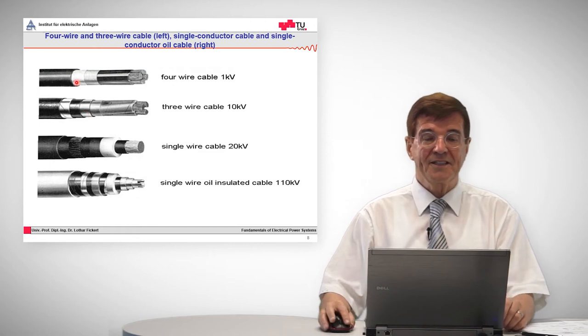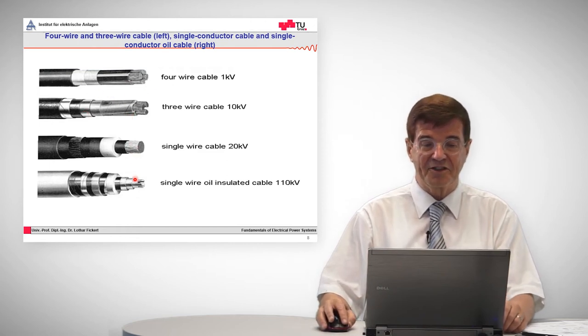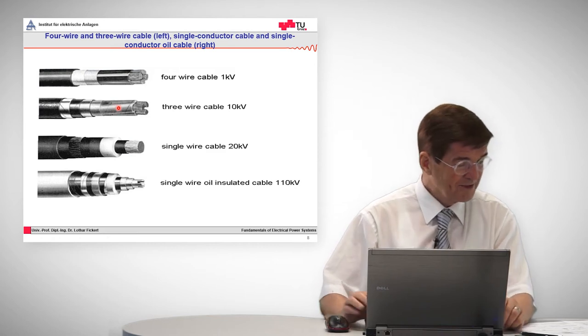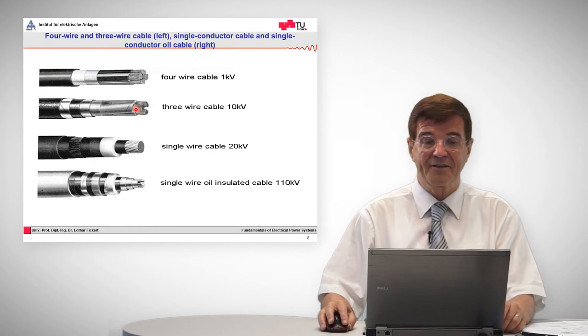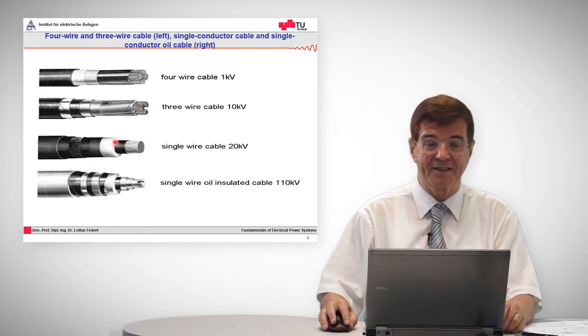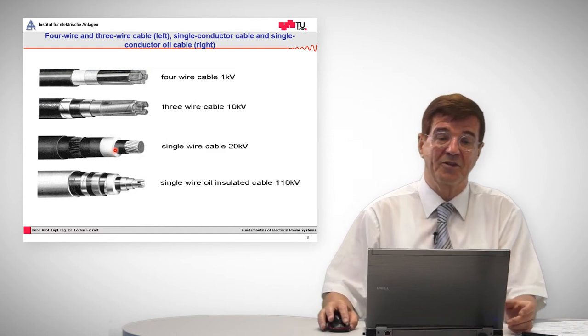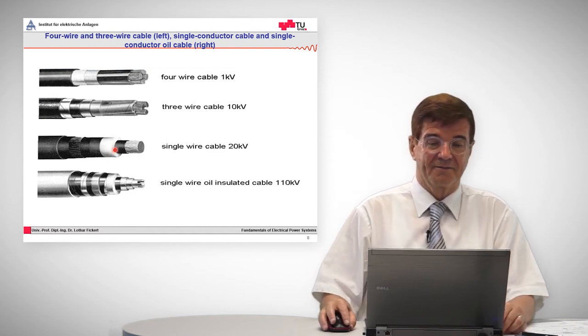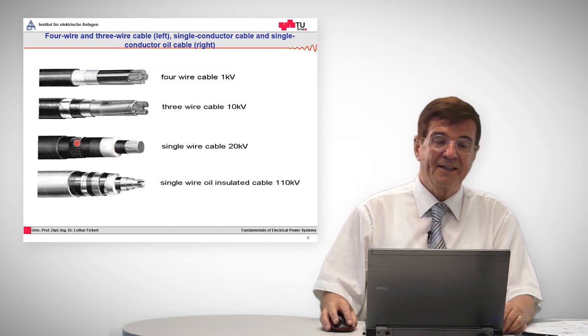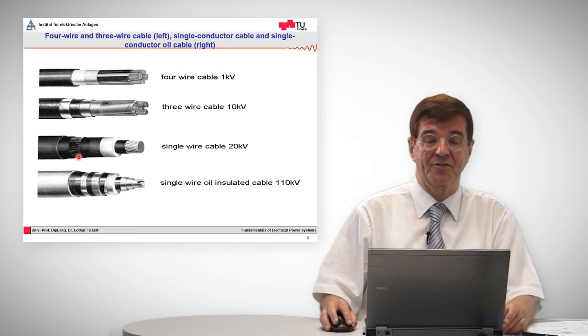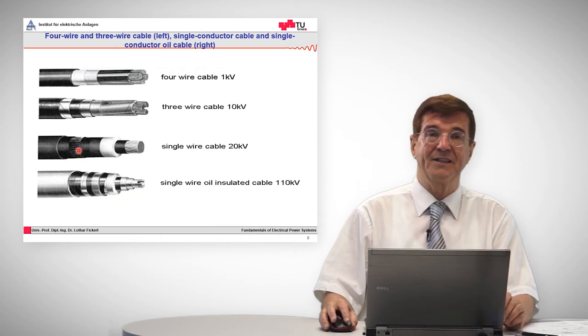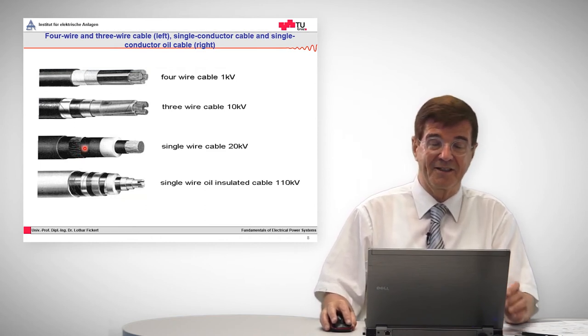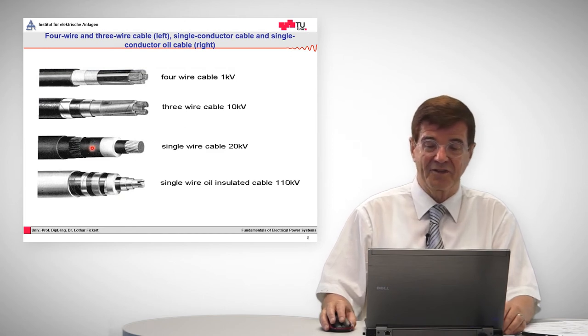Another technology is cables for low voltage, medium voltage, and high voltage. Such a cable is constructed in the way that we have the conductor in the center. Around the conductor we have the insulation which is made of polyethylene and other material. Then, importantly, we have around it another conducting shield, the so-called shield wires or shield, which is important to restrain the electricity inside of the cable, the electric field and the electric current in case of a fault.